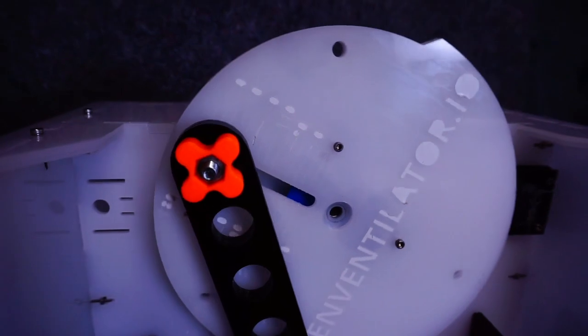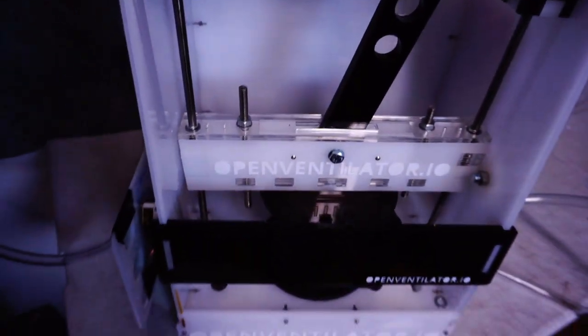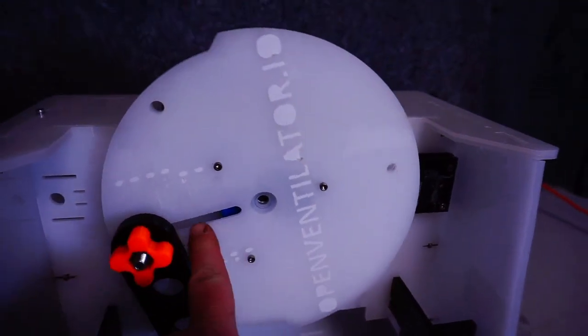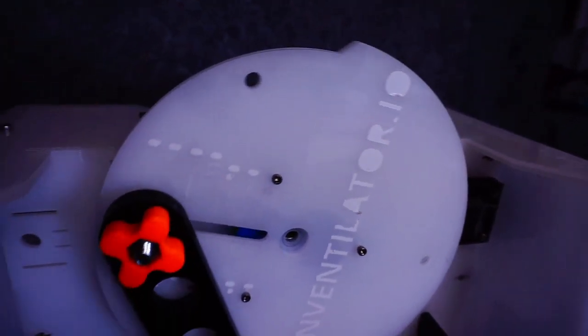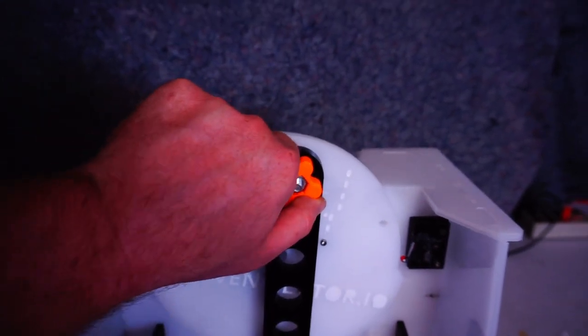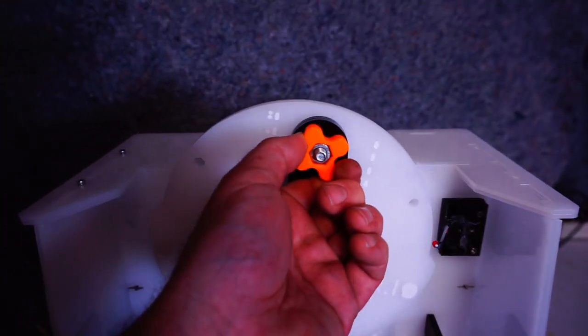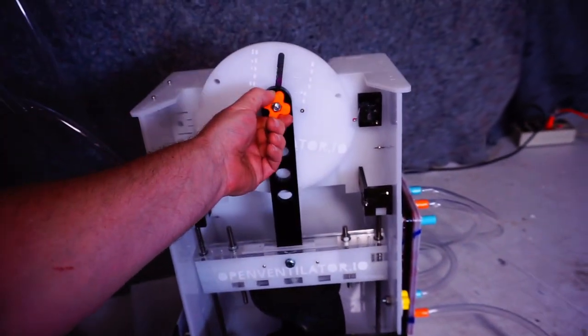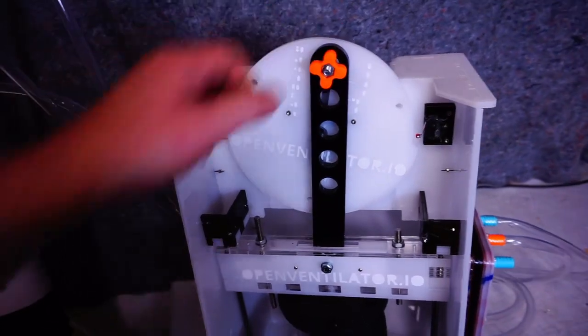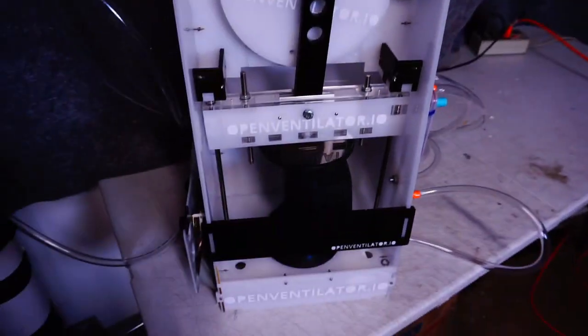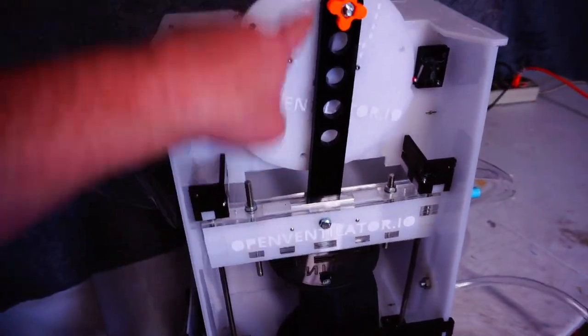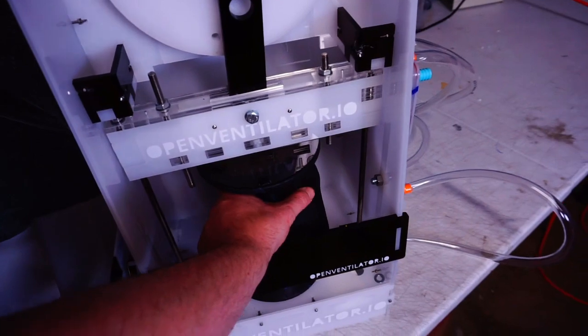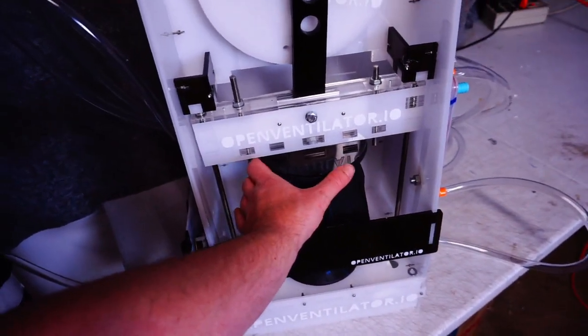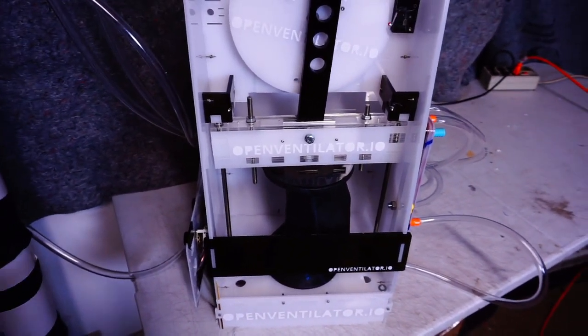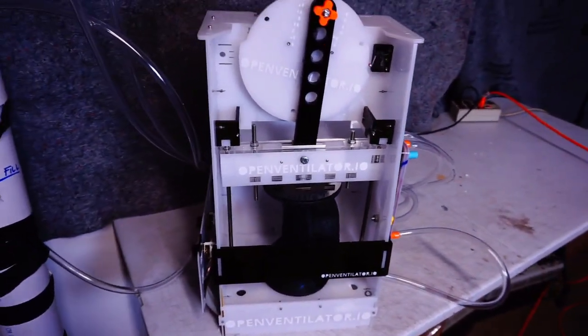Also, we can adjust the volume pumped by the pump by changing the crank arm length here. If I shut the machine off for a second. Hang on. You can just loosen this nut, change the length of this arm here. Okay, that's pretty simple. The volume pumped is not so simple as just the area of this piston times the stroke length, because this bellows is not 100% round or regular, and also because the pressure changes within the system, and so that would change induced volume.